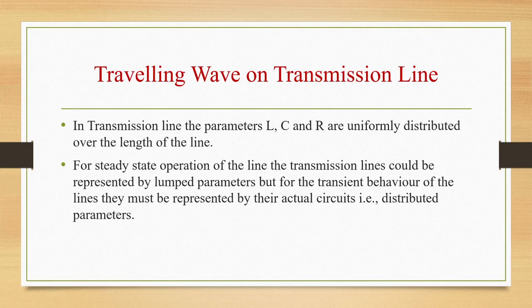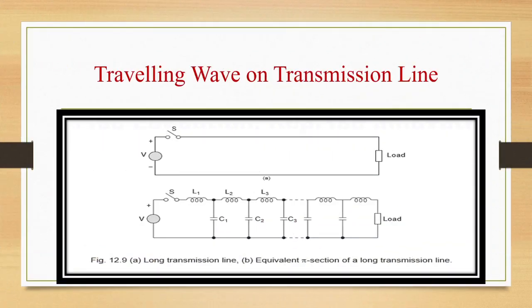In a transmission line, parameters L, C, and R are uniformly distributed over the length. For steady state operation they can be represented as lumped parameters, but for transient behavior they must be represented by distributed parameters. For a 50 Hz supply and short transmission line, sending end current equals receiving end current and the change in voltage from sending end to receiving end is smooth. This is not so when the transmission line is subjected to a transient.